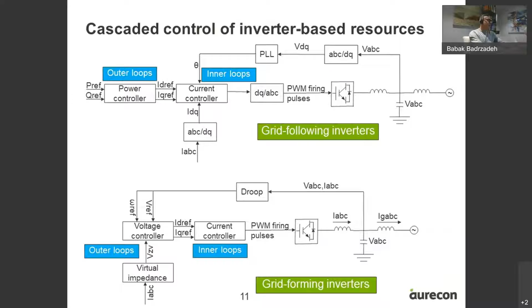Note that typically there is a factor of 5 to 10 times difference between the frequency, or clock speed, of the controls for the inner loop and outer loop. For example, if inner loops run at 10 kilohertz, which is the switching frequency of PWM, the outer loop could be somewhere like 1 or 2 kilohertz.